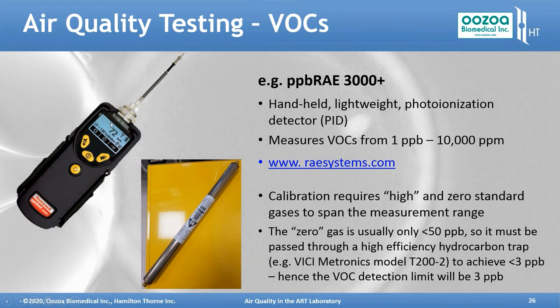Calibration of these devices requires a high and a zero standard gas in order to span the measurement range. The high is usually something like 10 parts per million, which for us is very high, and it might be a bit high. If you can get one more like 5, it's better, but the high one is okay. But the zero gas that's usually supplied, when you read the small print, only guarantees to be less than 50 parts per billion. And since that's the area we really want to be in, you need to do an additional purification of your zero calibration gas.